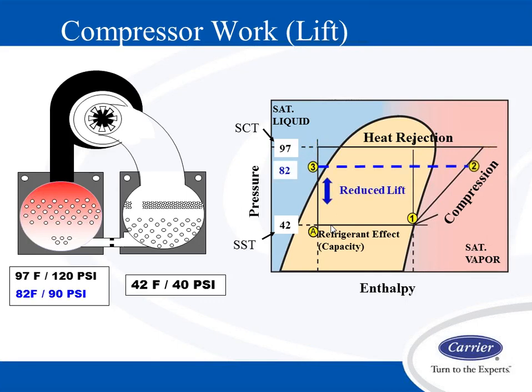When I can operate with colder condenser water, we reduce lift on a chiller. Let's say I have 70-degree entering water, 80-degree leaving, 2-degree approach. I have 82-degree saturated condensing temperature. If I'm able to operate with colder condenser water, I'm reducing lift, and I'm reducing kW on the machine itself. Lower lift, lower work equals lower kW.